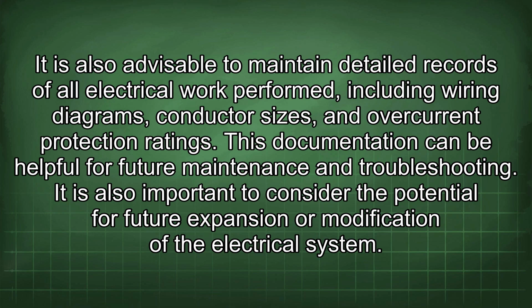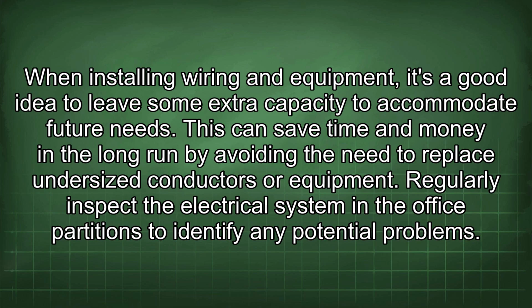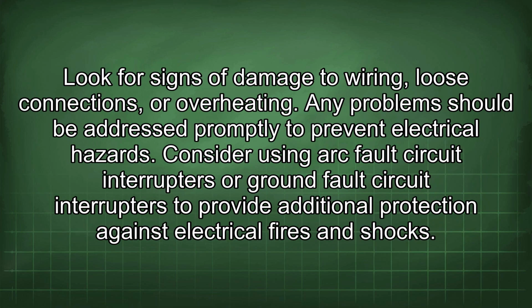It is also important to consider the potential for future expansion or modification of the electrical system. When installing wiring and equipment, it's a good idea to leave some extra capacity to accommodate future needs. This can save time and money in the long run by avoiding the need to replace undersized conductors or equipment. Regularly inspect the electrical system in the office partitions to identify any potential problems. Look for signs of damage to wiring, loose connections, or overheating. Any problems should be addressed promptly to prevent electrical hazards.